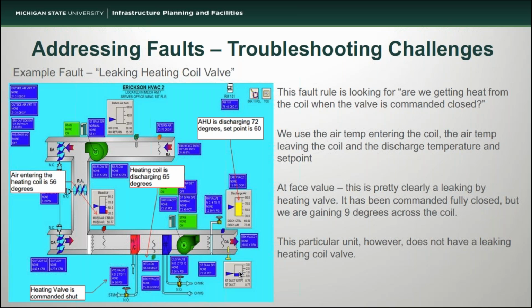In reality, we have replaced the heating valve on this unit twice, and because I knew that had happened, what we did instead was go out in the field, take IR images, and take readings around the air handler. What we discovered was that in this particular mechanical room, there's a very large steam pipe that runs over top of the air handling unit, and some of the insulation was no longer in place. It was creating enough heat on the top of the metal of the air handler that we were seeing a significant increase in temperature, but the heating coil valve was just fine.